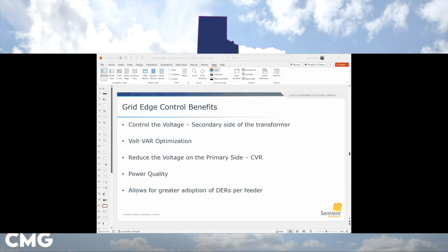Grid edge control benefits. So grid edge control - you'll see the device in just a minute - essentially when we say grid edge, we mean on the secondary side of the transformer, we're able to control the voltage. Once we control the voltage, we can optimize it and then reduce the voltage on the primary side to see some conservation voltage reduction. It also addresses power quality and allows for greater adoption of DERs per feeder.